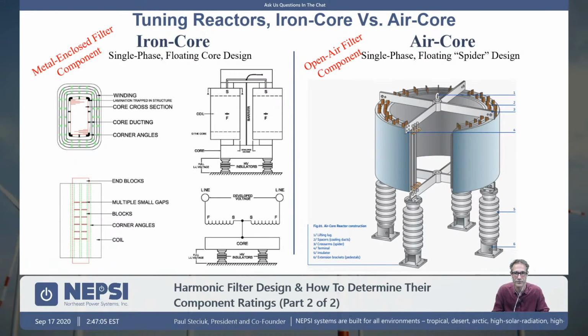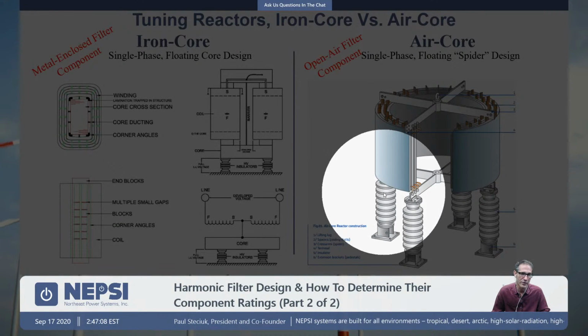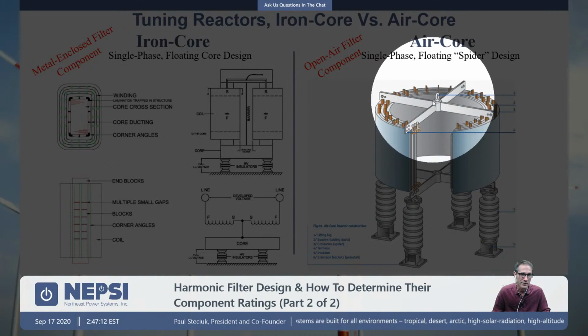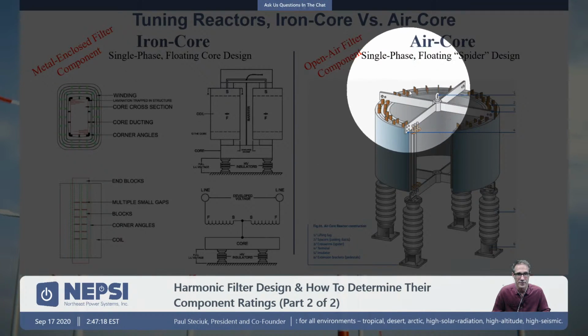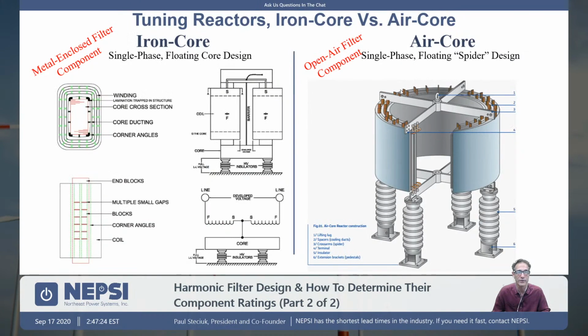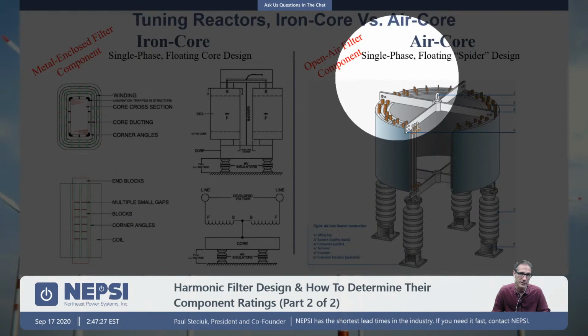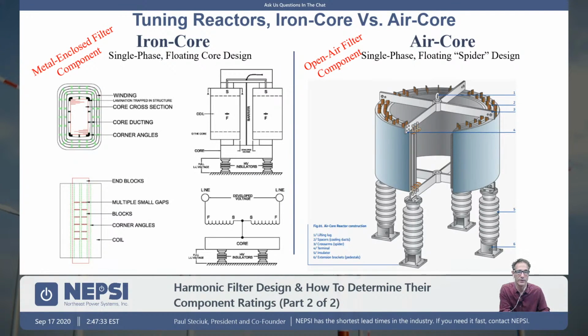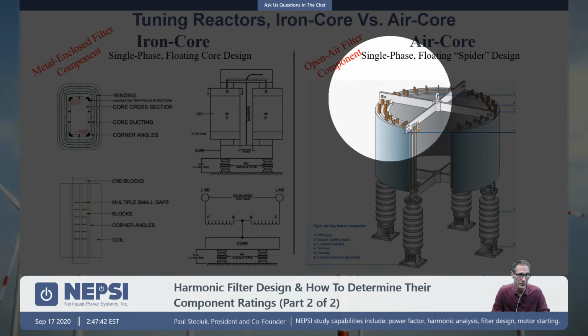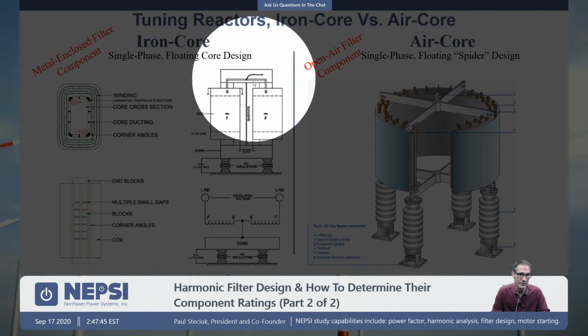Okay, so it adds to the reliability. The same thing is kind of being done here with air core reactors. If you think about the webbing here, it could be translated to the core over here. The core here actually holds the winding, and here the coil is wrapped around the webbing. So they are attaching basically the coil to the webbing. Okay, and then the webbing and the whole structure is supported on insulators. So they're elevating the voltage of the webbing to the voltage of the winding. And the same thing is being done over here. The winding is being tied to the core, and they're elevating the core.